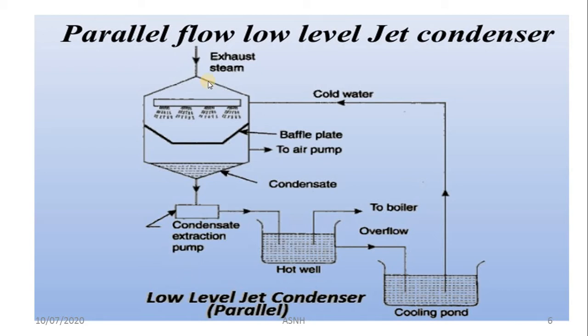So students, now we will discuss the parallel flow condenser. It is also called a low level jet condenser. Here you will get information about the components of the parallel flow condenser. This is the shell, the outermost part, which is made of corrosion resistant metal. Stainless steel is generally used. The steam enters from the top side. These are the baffle plates which allow the water to fall in the form of a spray. This is the line from the cooling pond which continuously supplies cooling water into the condenser shell. At the end there is a collection of the condensate.